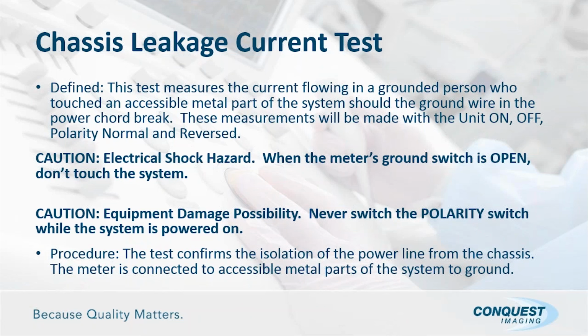Okay, the other thing, just a note on the Dale 601 for those of you who use the Dale 601, is as you're changing from, say, normal to reverse polarity, they want you to pause in the off position for a minimum of 3 seconds to prevent damage to the actual safety analyzer. So you shut your systems down manually. Once it's down completely, you go from normal to off and leave it in that position for approximately 3 seconds, minimum of 3 seconds, and then go ahead and go to the reverse position before powering it up again.